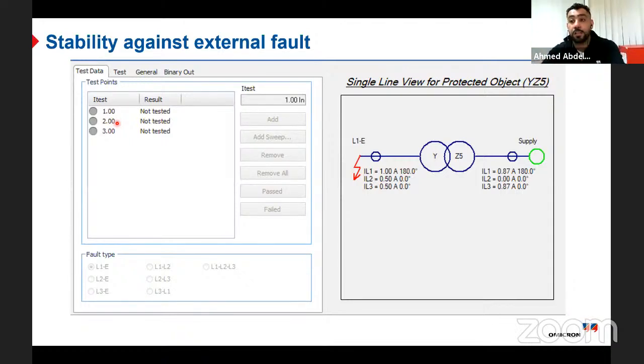So if you start doing the trip test and you find that your system is tripping all the time, you don't know what exactly the problem is. The problem could be in your calculation, in your CMC, in your injection, in your relay, or maybe it is a wiring issue. So to minimize the number of possible reasons for the mistake, what we do first is test stability against external fault at both sides, side 1 and side 2.